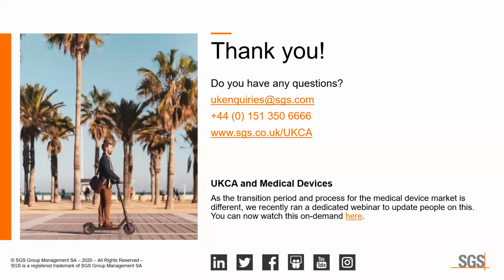The next question is, if we currently distribute a product into both the UK and EU, but our EU declaration of conformity is only in English, would we need to translate this into a different EU language? That is currently the accepted practice for CE marking. Of course, if you are UKCA marking in the future, that would only be valid for product in the UK anyway, so that wouldn't apply. If you're delivering the product into Europe, then it must be CE marked, so the same accepted practice would still apply.